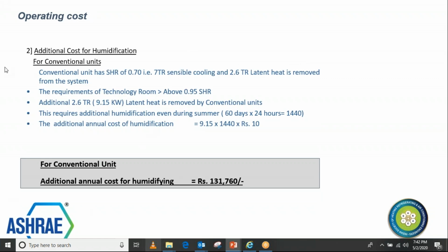Now, the other component was the humidification effect. As we discussed in the previous slide, the comfort air conditioning system has 0.7 sensible cooling and 0.3 latent cooling. Out of 10 TR, 7 TR is sensible and 2.6 is latent. This 2.6, when you multiply in kilowatt, comes to 9.15. This is the latent cooling capacity removed from the room by conventional units by overcooling, although this latent capacity was not required in the room because the requirement was sensible cooling. What does it mean? You are unnecessarily throwing the latent capacity out of the room, and then the room will become much drier, which means you must add humidification in the room.